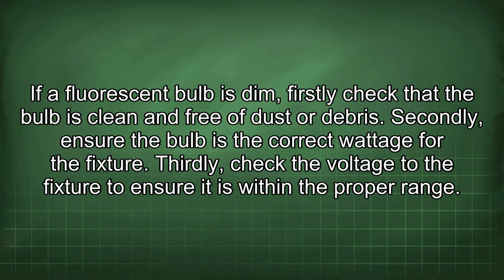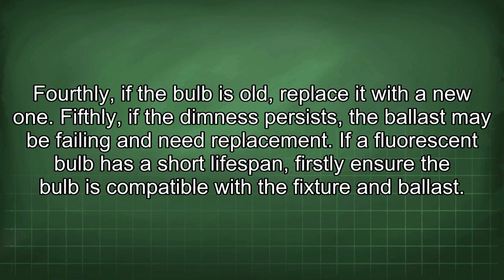If a fluorescent bulb is dim, firstly check that the bulb is clean and free of dust or debris. Secondly, ensure the bulb is the correct wattage for the fixture. Thirdly, check the voltage to the fixture to ensure it is within the proper range. Fourthly, if the bulb is old, replace it with a new one. Fifthly, if the dimness persists, the ballast may be failing and need replacement.